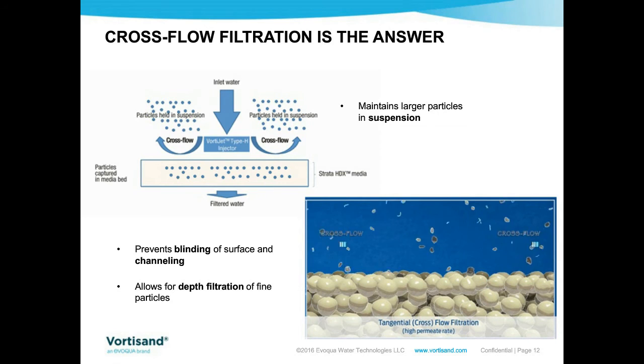I think it's time to look a little bit more at cross-flow microfiltration, microsand filtration, and what benefits it can bring to your applications. So first off, it's important to say that cross-flow microsand filtration is media filtration, and it takes the shape of pressure vessels inside which we put a layer of media. Contrary to conventional filtration or multimedia filter, there's only one layer of media in cross-flow microsand filtration. It's a monomedia filter. And just like I was talking about a little bit earlier, it relies on 2 things. First off, a very specific type of media, and also a hydraulic pattern inside the filter, and we call it cross-flow, and it's represented here at the top left.